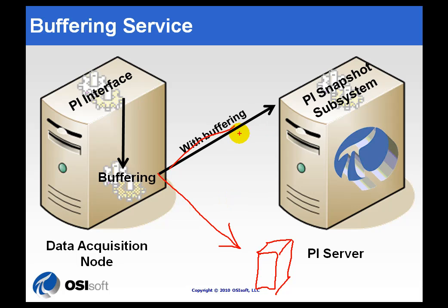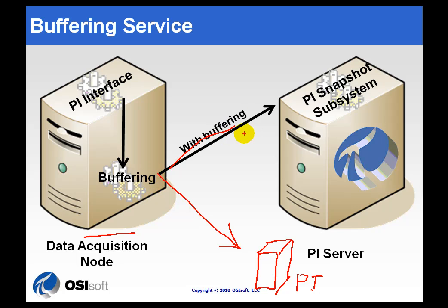When you're doing N-Way Buffering, you want to make sure there's exactly the same data on both PI Servers. If this is a PI Server in a Collective — a Collective is implemented as part of PI High Availability — the whole goal is completely the same information on both servers. If you do the data compression on the Interface Node, what you end up sending is exactly the same data to both servers.